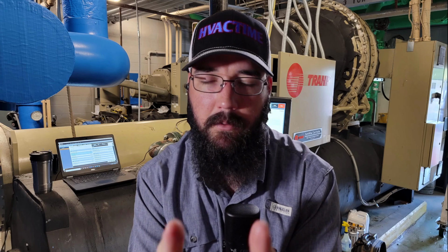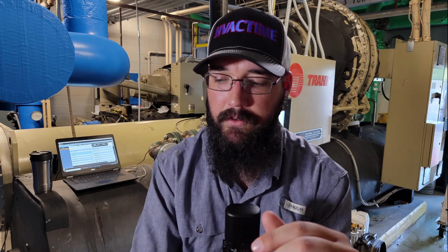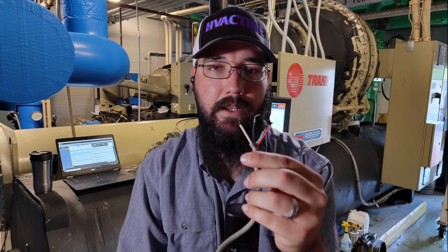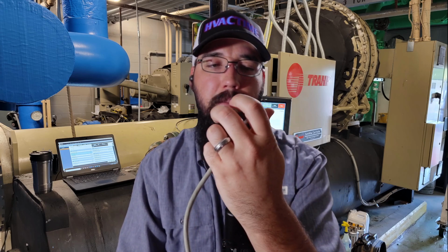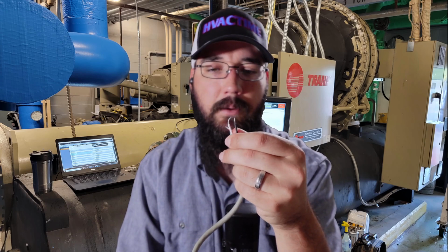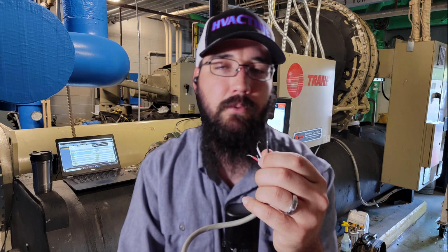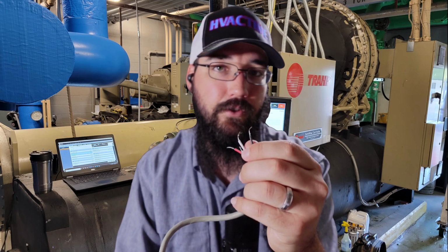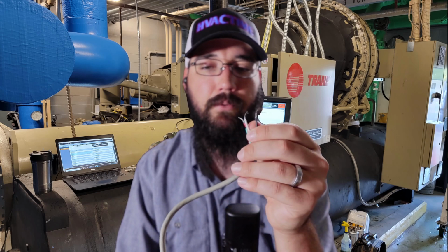it's not that this doesn't work, okay? I'm not saying this doesn't work, but you have to be aware of how it works. They think that these are constant pulses to where you can just put your meter across these leads. So in this example here, we have a 4 lead, and if I just put my meter across these 2 leads, I'm just going to see my voltage, and that's not what actually happens. And this also depends on your meter and how fast its reaction time is for the reading. But if your meter is going to show a fluctuation, which is really what you're looking for at that point, is do you see the pulsing when it goes to try to move the valve?